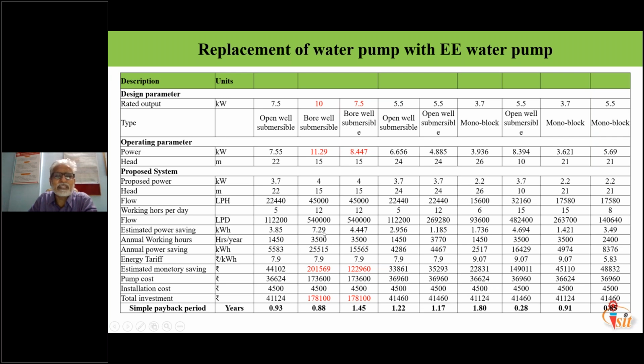The estimated power saving is 7.29 kilowatt hour for one pump and 4.47 kilowatt hour for the other, with annual working hours of 3,500. Annual power saving is 25,000 units for the first, since it consumes more, and 15,000 units for the second. With a fixed energy tariff, the estimated monetary saving is 2 lakh and 1.22 lakh respectively. Pump cost is the same for both, 1,73,000, plus some initial installation cost. So the payback is below 1 year for one, and 1.5 years for the other.